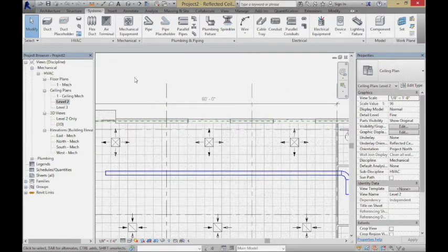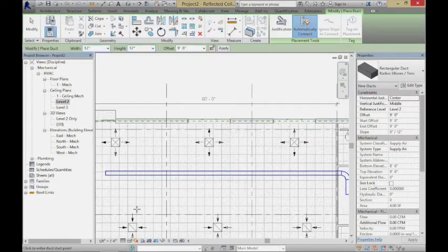Okay, now as I go through and connect these things actually to the terminals, what do I want to do? I tend to have other pieces of duct that'll come off and run over close. You will find that I tend not to connect them directly because even with a level 9 and the 8 feet there, it may not actually connect directly with a lot of hard ducting in there. I might have to actually raise it up a little bit higher or put a different sort of system as opposed to radius elbows. Might have to have ones that have taps on them so that it could actually just attach the terminal right to the bottom of the piece of ductwork.